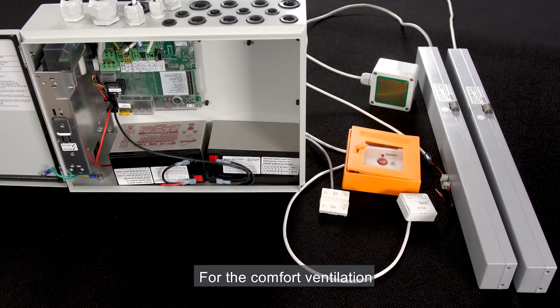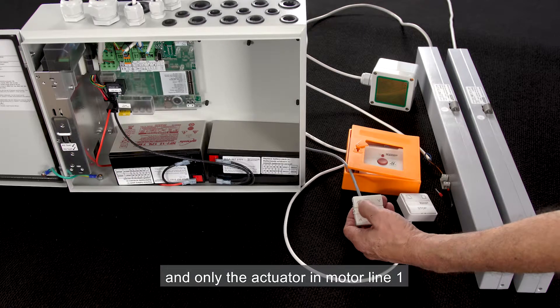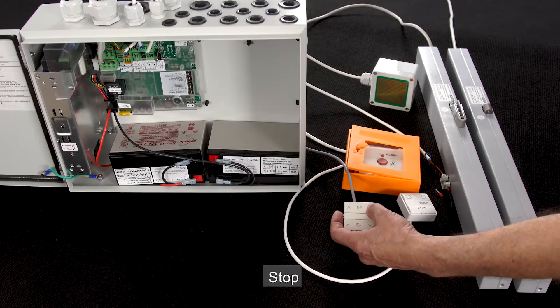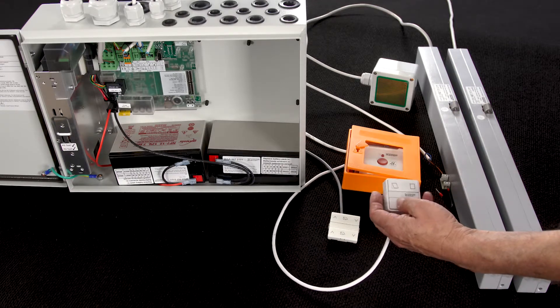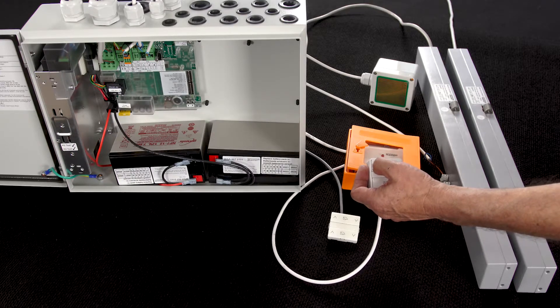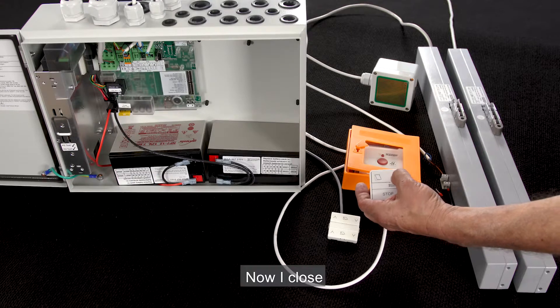For the comfort ventilation, we have the manual override switch that is configured to operate Motor Line 1. I press the open button and only the actuator in Motor Line 1 is opening. Stop. Close. The manual override switch connected to the break glass unit should activate all the actuators that are associated with this smoke zone. I press the open button and both actuators start opening as expected. Now I close.